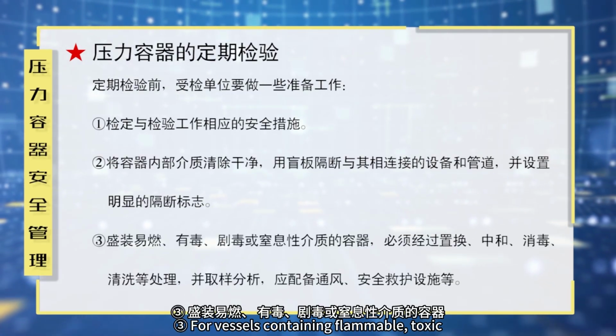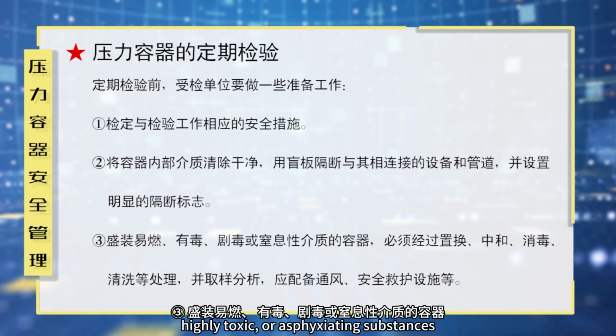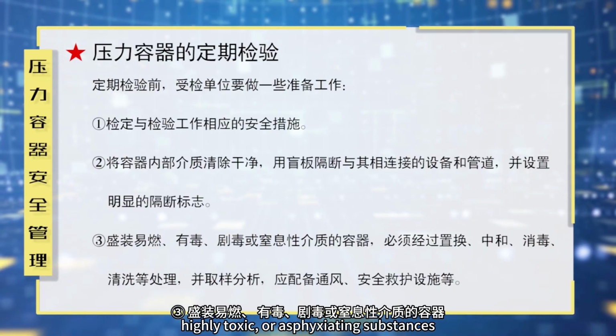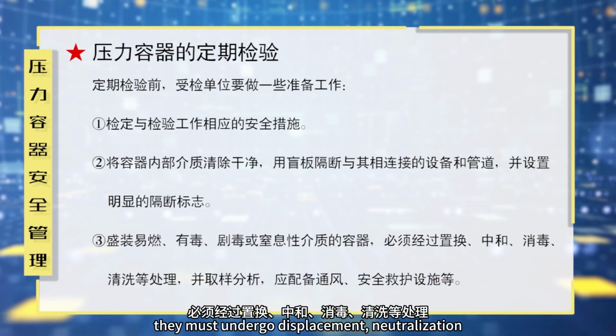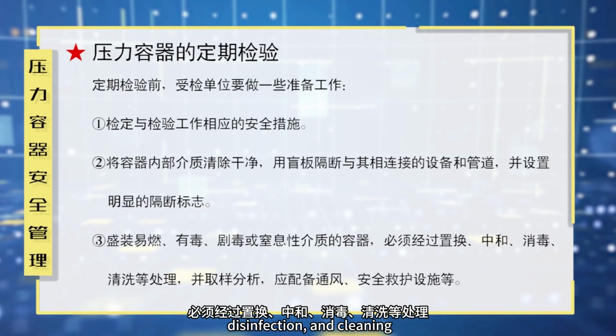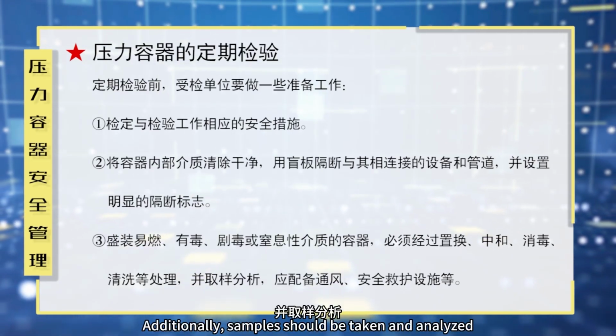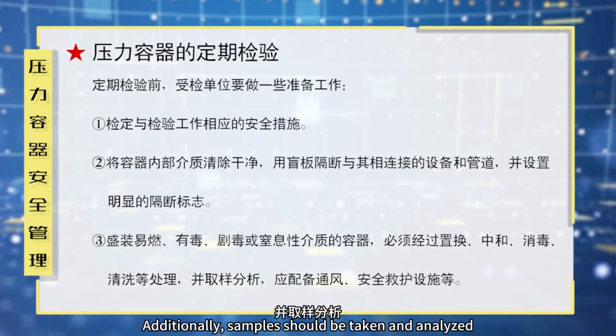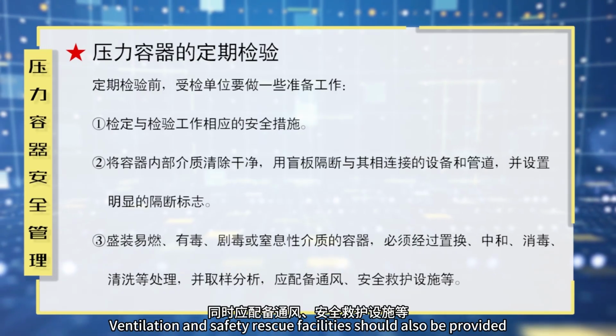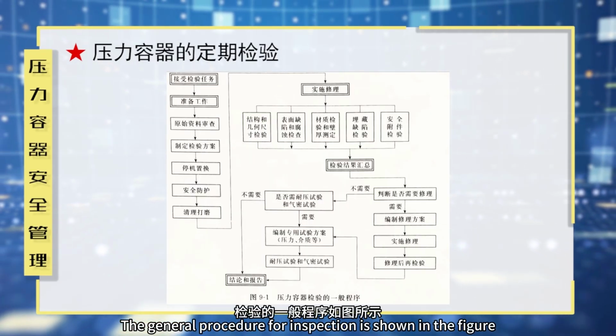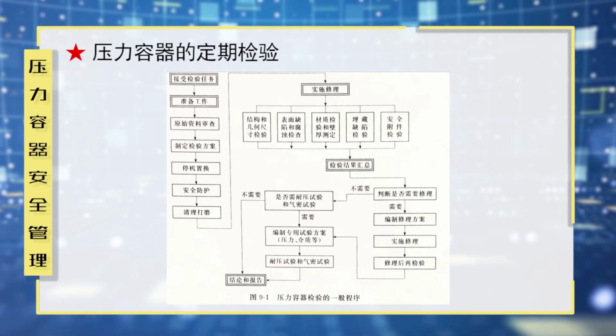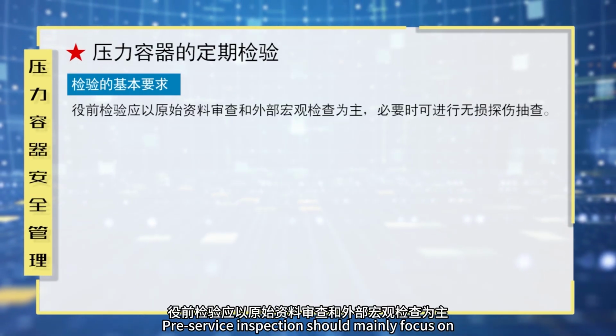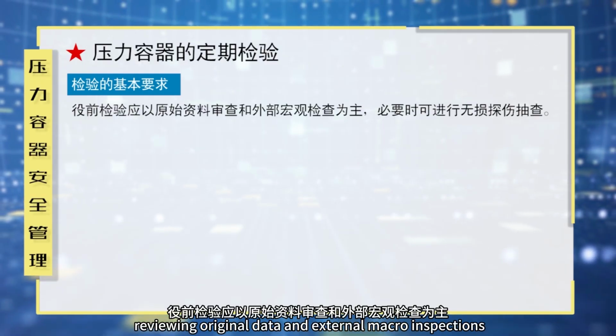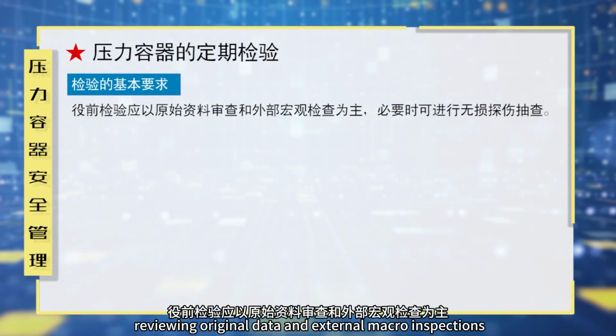Third, for vessels containing flammable, toxic, highly toxic, or asphyxiating substances, they must undergo displacement, neutralization, disinfection, and cleaning. Additionally, samples should be taken and analyzed. Ventilation and safety rescue facilities should also be provided. The general procedure for inspection is shown in the figure. The basic requirements for inspection. Pre-service inspection should mainly focus on reviewing original data and external macro inspections.